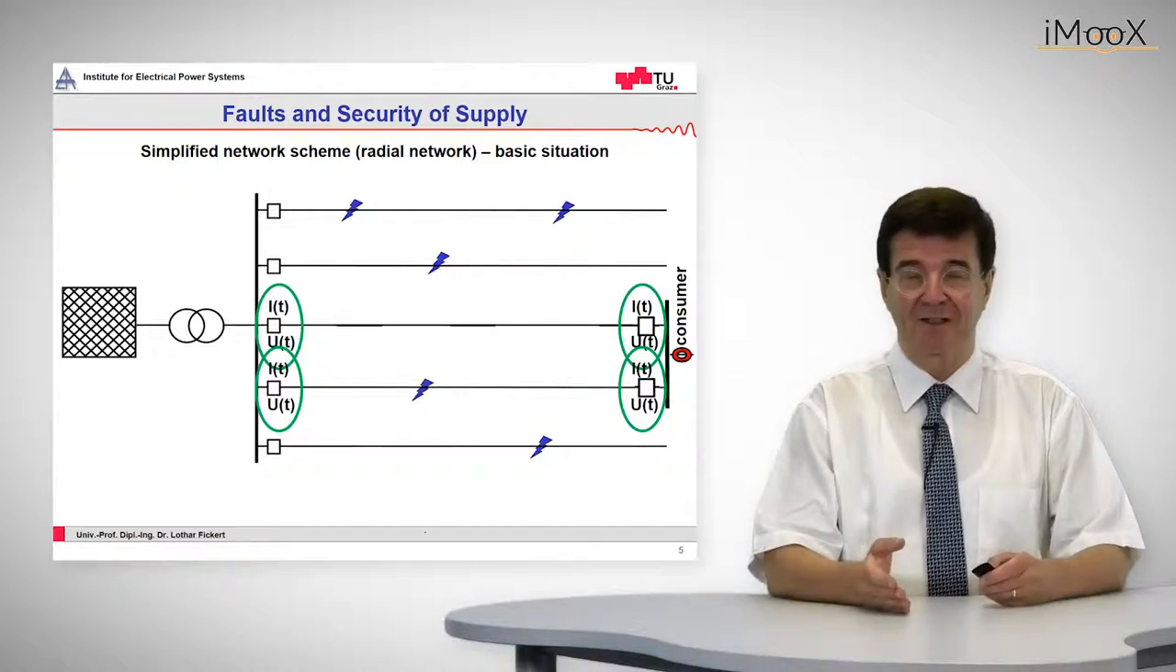The protection in this case should consist of four protection devices, two at each end. And these protection devices should especially on the consumer side be directional sensitive. That means they must compare the direction of the current, that is the phase relation between voltage and current. And this is indeed done by establishing a voltage transformer connection.